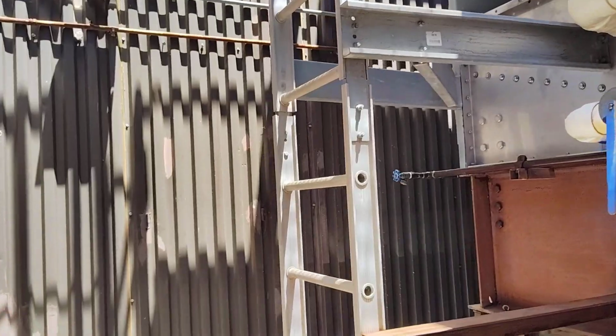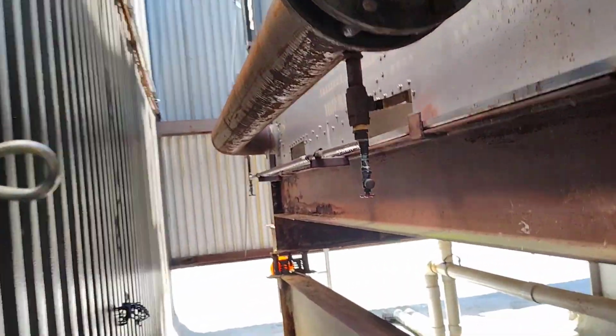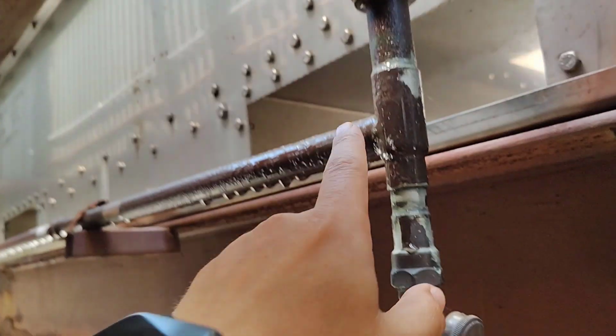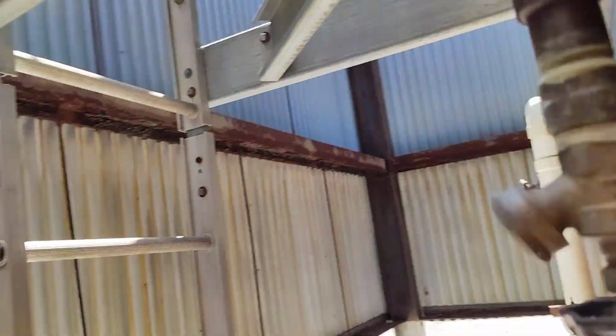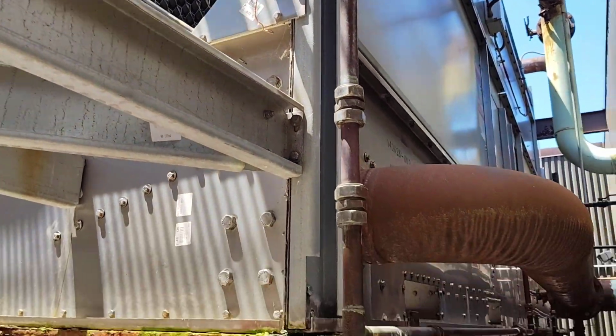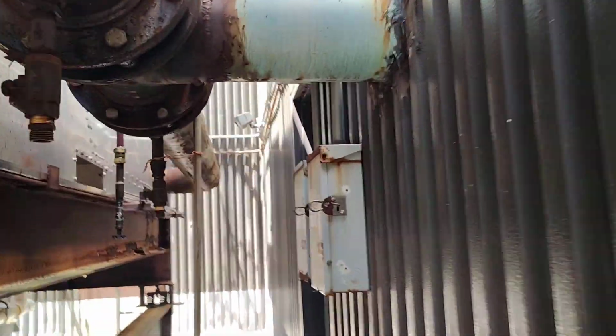Okay, the same on the other side. As we are going here, this side, it will be here. This is the water supply that's coming from the room. This is a drain at 90 degree, and we continue. Another drain. This is closed. This is closed, and it's going up. This is the makeup water. Okay, so we finished this line as per the drawing.